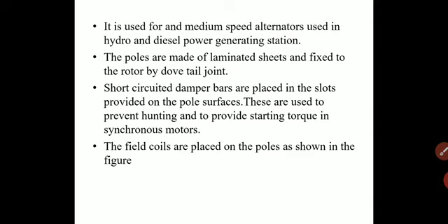Here you may have the question, what is hunting? It is the momentary speed fluctuation in an alternator. And for your knowledge, under normal running condition, the damper winding does not carry any current because the rotor runs at synchronous speed. The damper windings also tend to maintain balanced three-phase voltage under unbalanced load conditions in the case of an alternator.